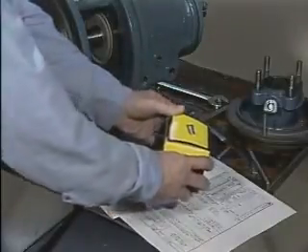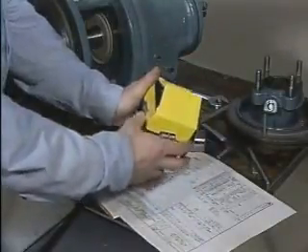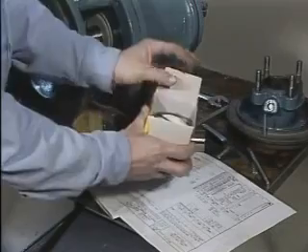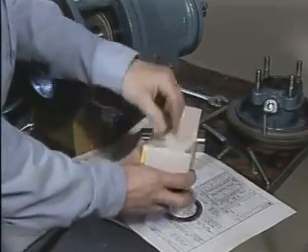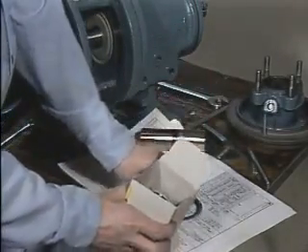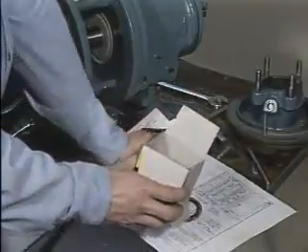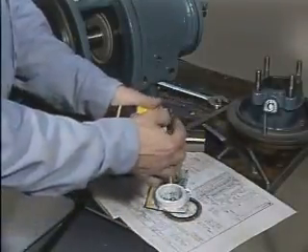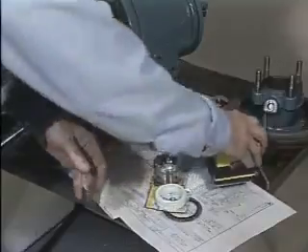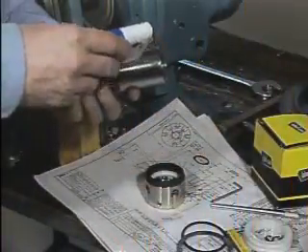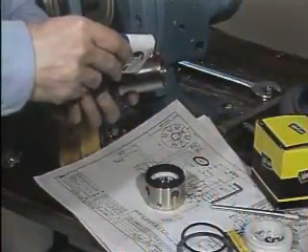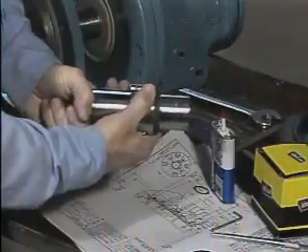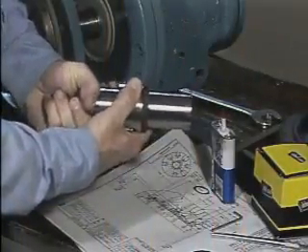First, the mechanical seal components are inspected for defects or damage. These components include O-rings, a mating ring, and a pre-assembled rotating element. The new gaskets that will be used should also be inspected. Any parts that fail the inspection should be replaced. Next, a small amount of lubricant is applied to the shaft sleeve. Then the rotating element needs to be positioned on the shaft sleeve.